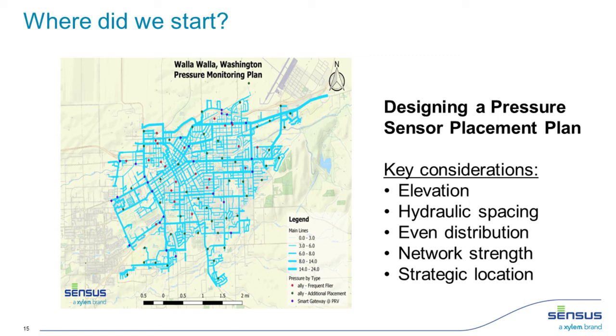Let me jump in there too. You were right about the alarms. If the smart gateway or the Ally detects an alarm, they're measuring every hour. So say they have a 1-hour MSR measurement interval that's broadcasting every four. If it detects an alarm, it will send a broadcast out at that measurement interval. So if you're on hour two and get an alarm during that hour, and it sees there was an alarm message from 0 to 59 minutes of when that occurred, it's going to send that up and say, hey, here's an alarm on the system. That will give you the text notification. For the smart gateway, it's the same thing, whether it's set on 5 minutes or 15 minutes.